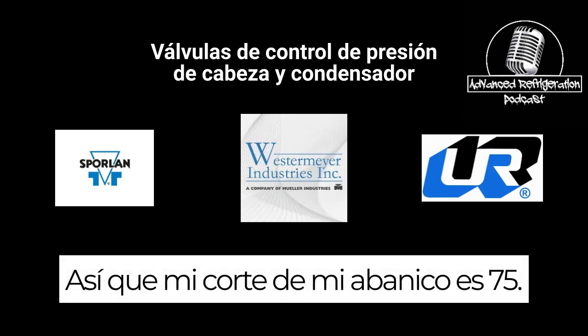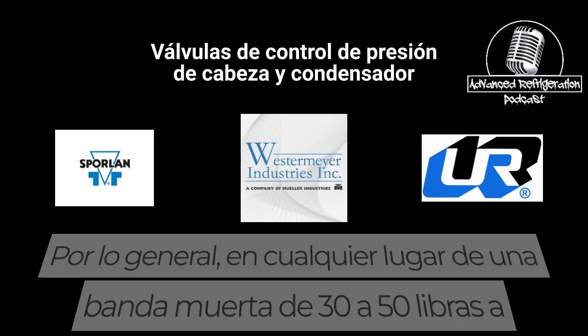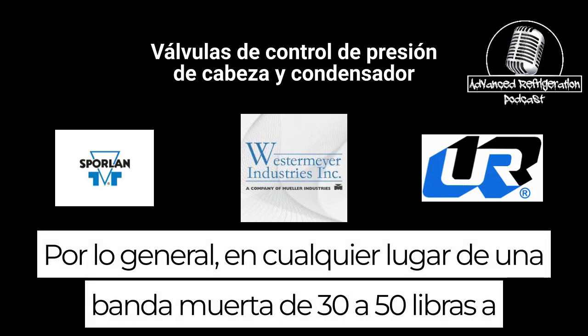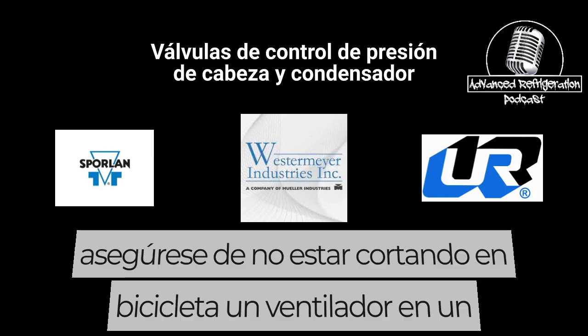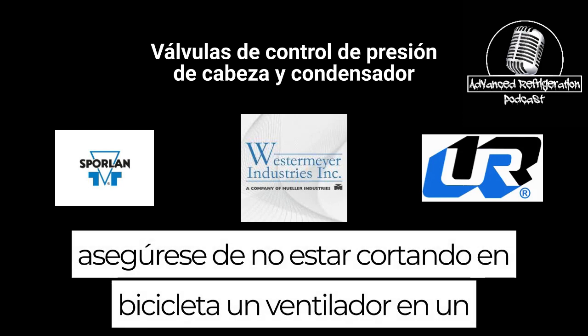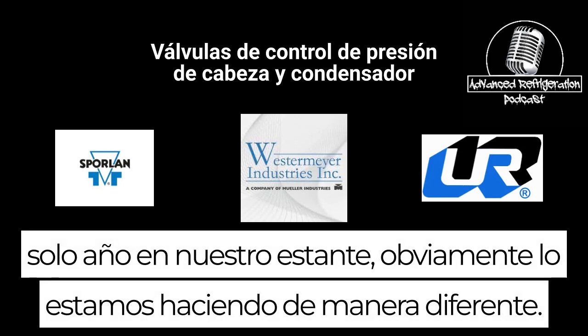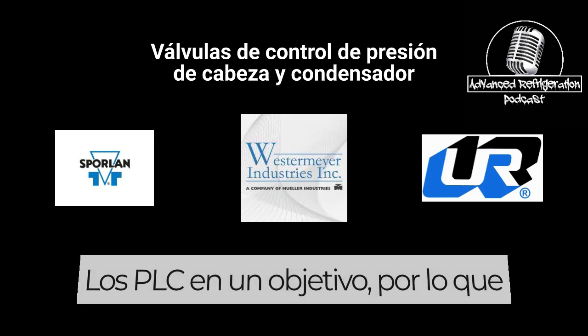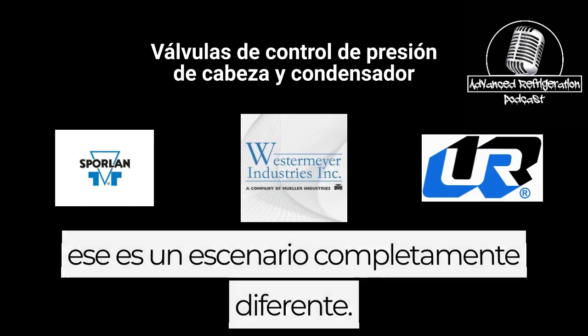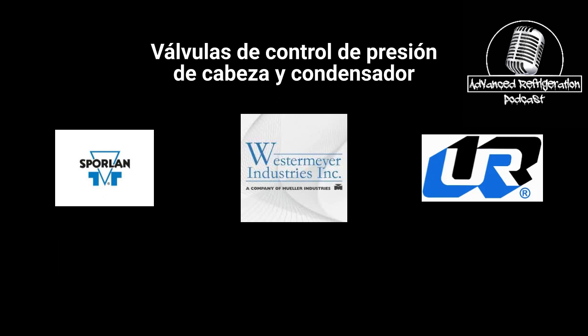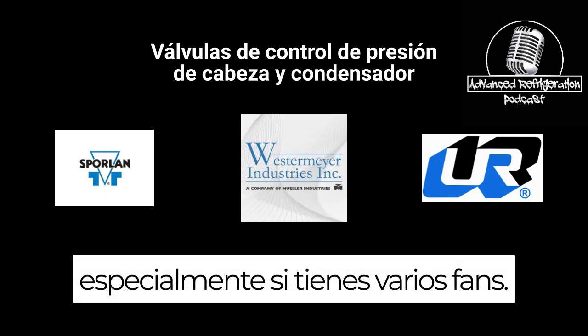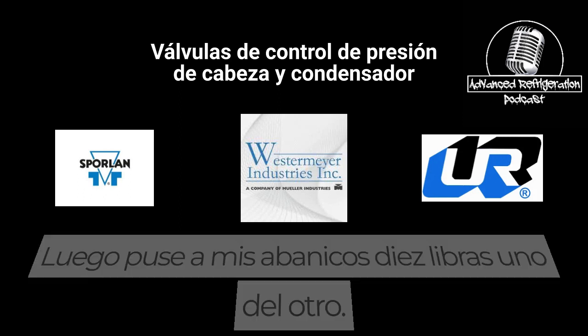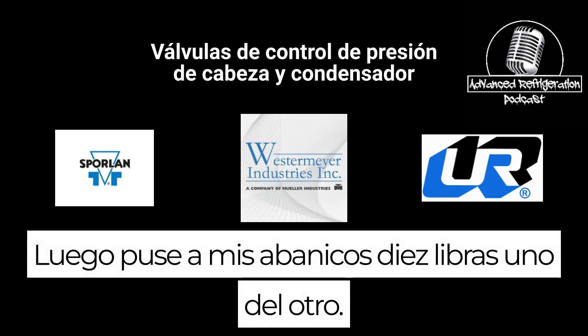So my cutout of my fan is 75, usually with anywhere from a 30 to 50 pound dead band to make sure you're not short cycling a fan on a single unit. On a rack, obviously, we're doing it differently. The PLCs are cycling fans to a target, so that's a whole different scenario. That's a lot smoother. But you're going to have a swing, especially if you have multiple fans. Then I set my fans 10 pounds from each other.